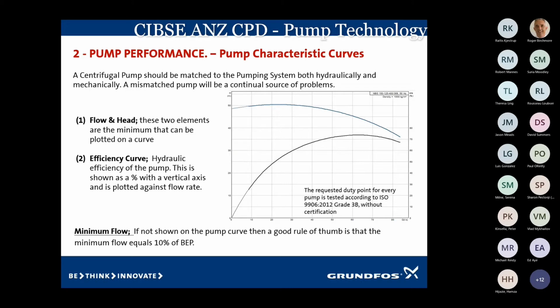Minimum flow is always around about 10% of the best efficiency, and that's based on cold water. So in this particular case, minimum flow would be around about 6 litres a second. If the water temperature is higher, I always allow a little bit more, just to give you a bit of safety, because you don't want heat building up inside the pump housing.